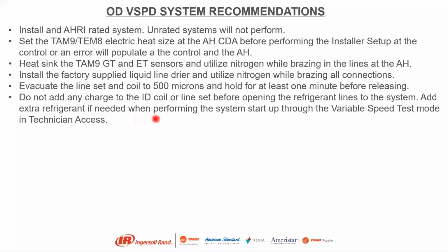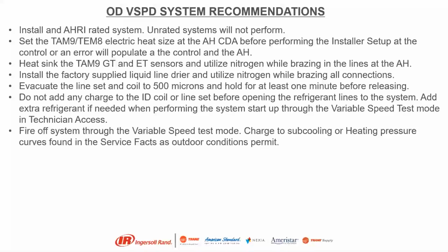Add extra refrigerant if needed when performing the system startup through the variable speed test mode and technician access. Again, we do not recommend adding charge because it's set for a certain coil, and we install so many different AHRI matches that it's not precise. Fire off the system through the variable speed test mode. And then you're going to charge by the subcooling and heating pressure curves. So in cooling, you're going to charge by the subcooling, or you're going to use the heating pressure curves found in the service facts.